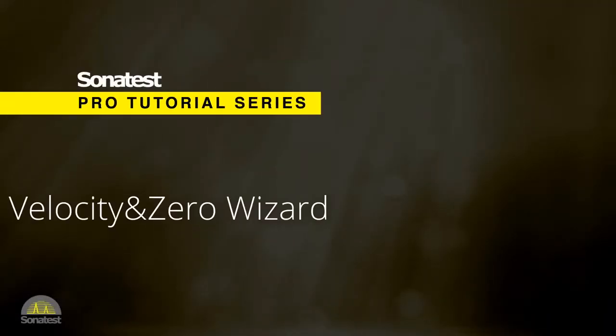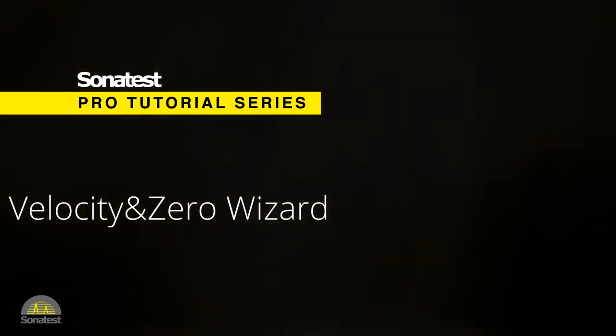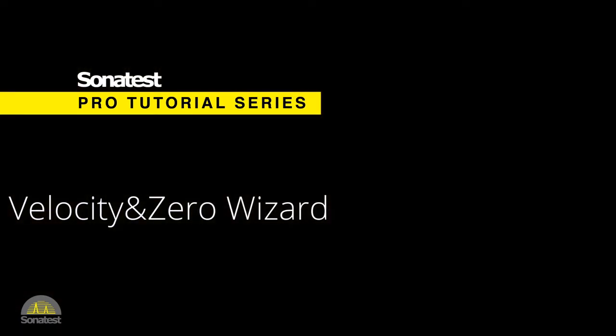Hello everybody, today's tutorial is about velocity and zero calibration. This calibration is setting the speed of sound value of the calibration block material and the appropriate delay 0 for the beam used in the calibration.